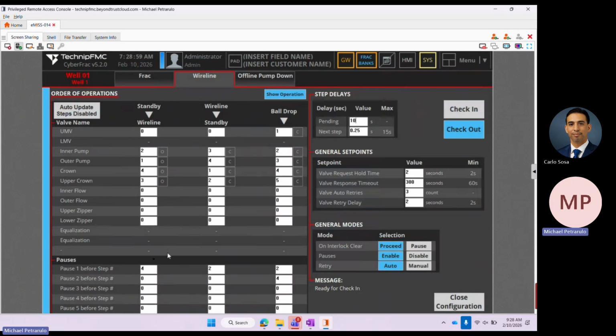It's just a way for me to add some time because sometimes people are a little more cautious - they don't want the sequencer to start right away, they might want to ease into it. So the pause requires some interaction from me, right? It requires an action from the HMI to resume. Yes. And the delay just continues, takes a little extra time. Yes. Okay, gotcha. So typically we don't put a pending delay, we just go right into the sequencer. It's set to 1 by default - this is the delay in between steps.